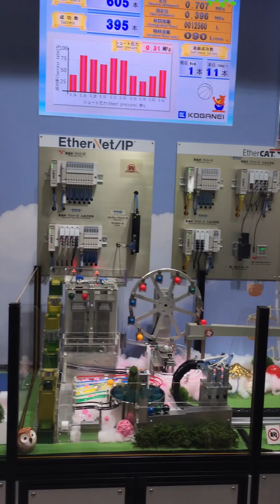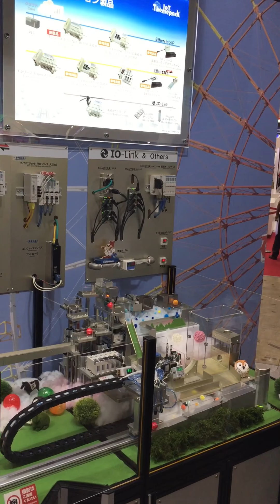IO-Link is not a protocol. Ethernet IP and EtherCAT are protocols. IO-Link is not a protocol. It's just a way of connecting to the other components. So you can take an IO-Link master, and you see the green wire coming out of the top? You can get one that has a protocol that matches your other protocol. So you can get an IO-Link master which has an EtherCAT protocol cable ready. Once you put that on your machine, you connect everything after through IO-Link, standard cables, nothing special, and then the IO-Link master converts that to the protocol of your PLC.